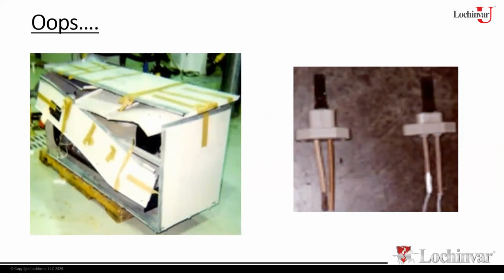The igniter is an OEM component, and this is what can happen if you use a non-OEM igniter. This is an older Copper-Fin 2 product, and as you can see, it's kind of disassembled, and the reason is because of the igniter. They had what we call a rapid expansion of gas and air inside the combustion chamber, and they basically sent the unit to us. This is how we received the heater. As we were expecting to find out what happened, we pulled the igniter out. The igniter we pulled out is the one that you see on the right side here. What should have been in it is what's on the left side.